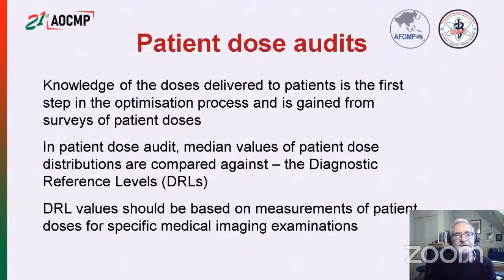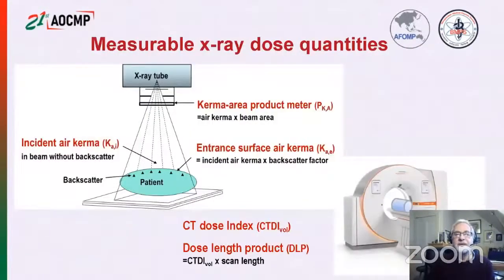So let's take a look at patient dose audit. This requires knowledge of doses delivered to patients. That's the first step really in the optimization process. So in patient dose audit, median values of patient dose distributions are compared against diagnostic reference levels. And then the DRL values should be based on measurements of patient doses for specific medical imaging examinations. And the sort of measurable X-ray quantities that might be used: kerma area product, incident air kerma for radiography, CT dose index and dose length product for CT.